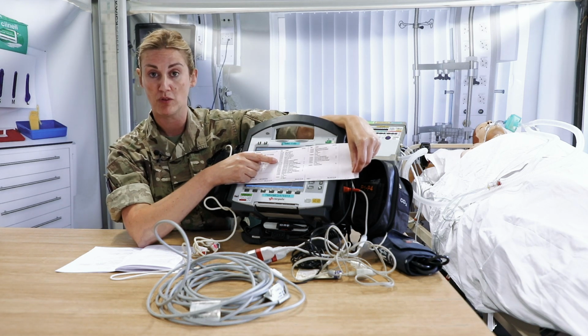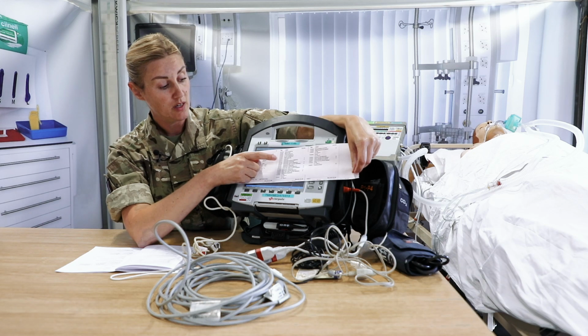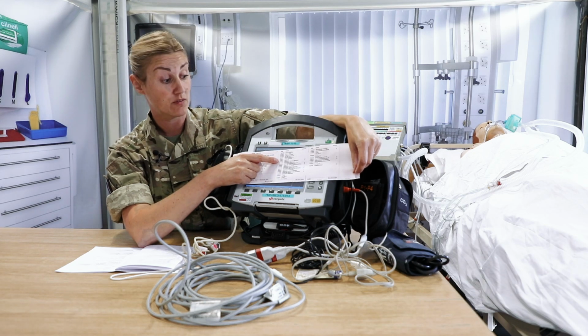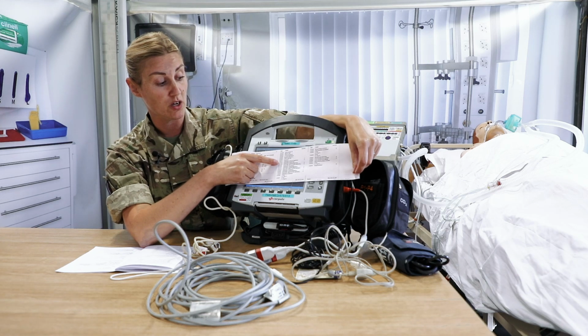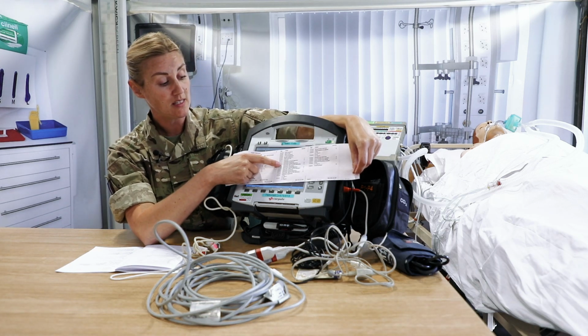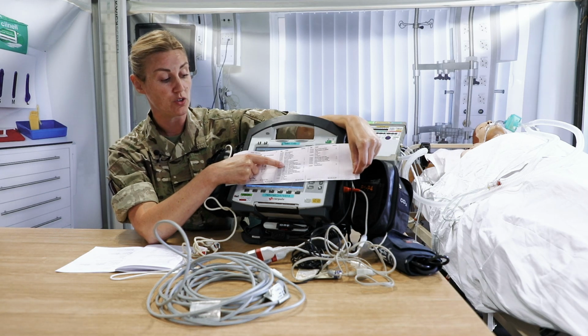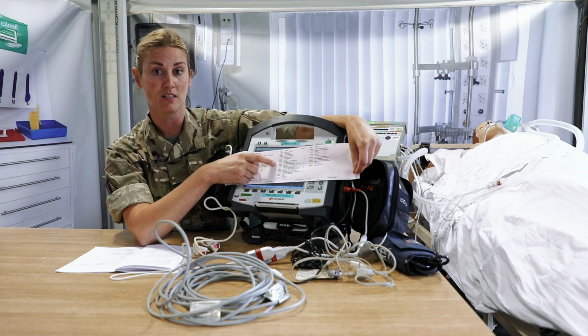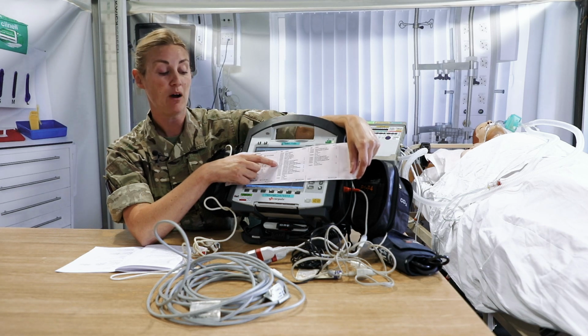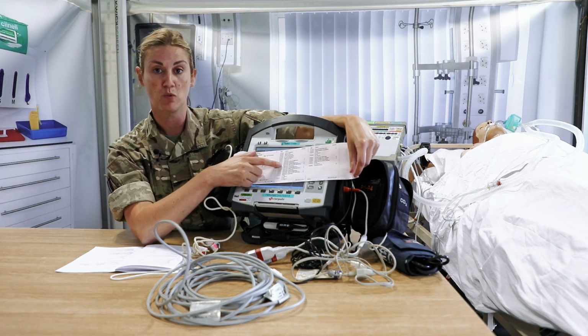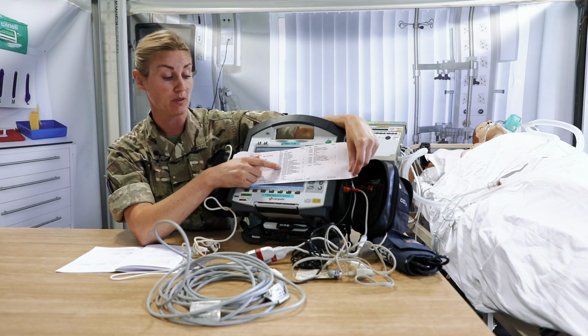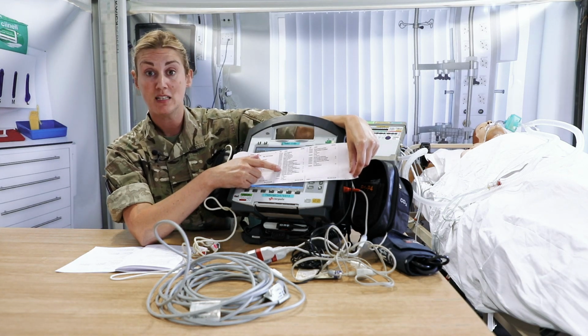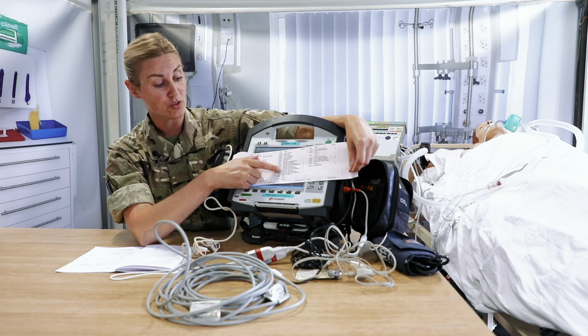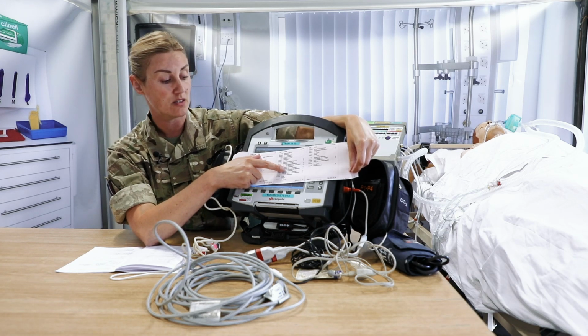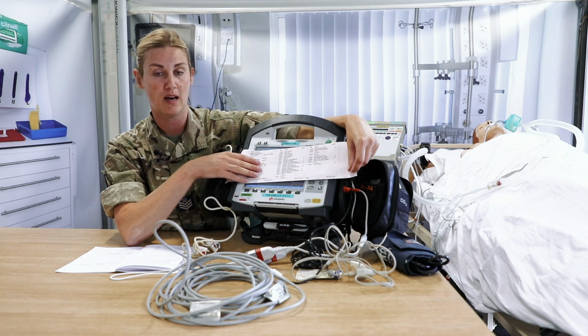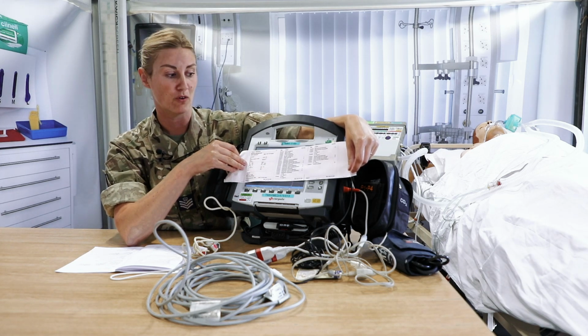And then we're going to work our way through those 3 defibrillator checks that we performed. So the first one is that the defibrillator charged up, so we see it's got a manual charge up here and that it deactivated. The next test was through the patches, so we charged to 200 and we shocked at 207. The amount of joules that it will deliver is around about 10% above and below, which is absolutely fine. And the final test was via those paddles, so we charged at 200 and it delivered 208. So the defib seemed to work absolutely fine, and our browser printout has confirmed that for us.